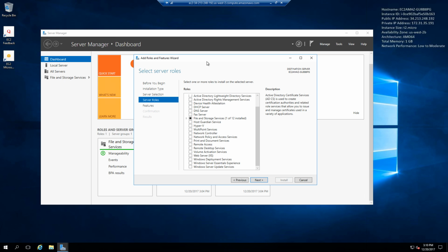Now, if you wanted to see the graphics from all three of those, how would you tie those together? You would use some sort of higher end system that all those would feed into, and you'd have a standard graphic. That way you had one place to go to for graphics, one place for trend storage, one place for alarming. That's the problem that a server solves for all these supervisory devices. So when do you use a server?